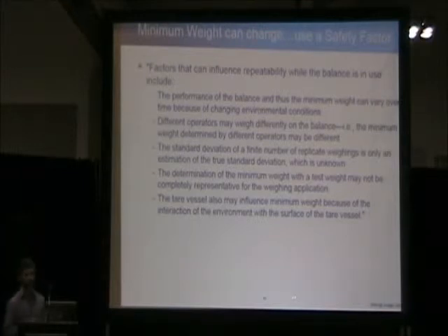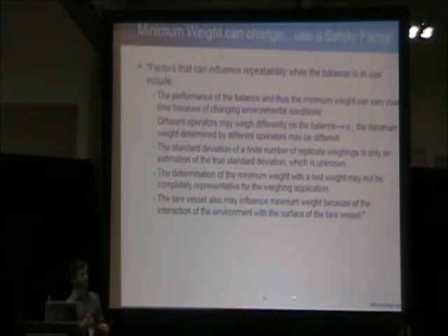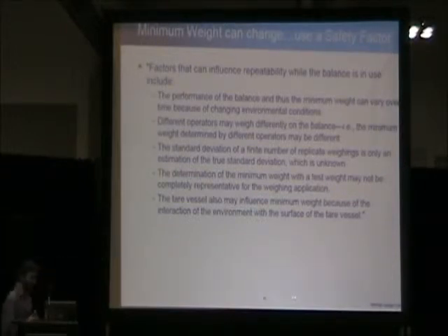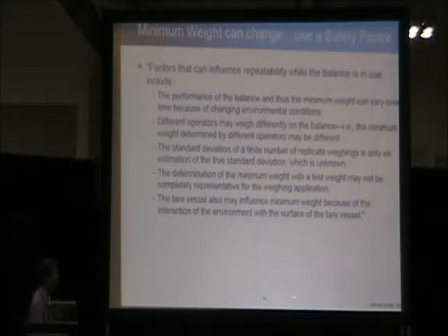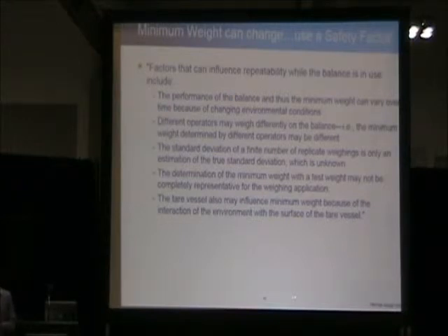You tested it in a very stable environment that is temperature and humidity controlled. But then you end up moving that instrument to another facility or to another location. And you retest it, and you get roughly the same minimum weight. But again, this is still in the month of June. What happens throughout the lifespan of your instrument, especially in between calibrations, is that the weigh cell actually drifts out of calibration. This is due to, again, the environmental factors that I discussed earlier, such as electrostatics, changes in temperature and humidity. The fact that different operators that use that instrument might have a different weighing technique.